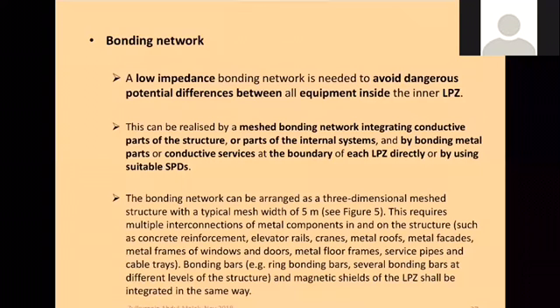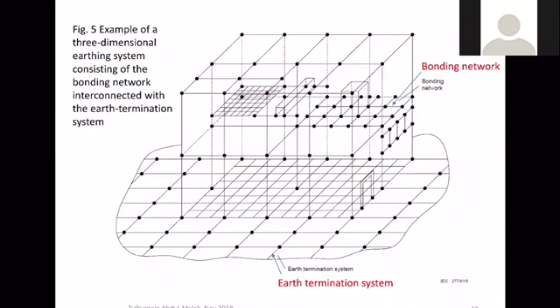A low impedance bonding network is needed to avoid dangerous potential differences between all equipment inside the inner LPZ, and this can be realized by a meshed bonding network as shown here. As you can see, the earth termination is under the soil, but for each level of the building you can see many metal works, and these need to be bonded together, as well as the incoming lines need to be bonded to the earth termination system. So the whole thing becomes the earthing system: the earth termination system plus the bonding with all the connected wires, as well as the metal works at each level.